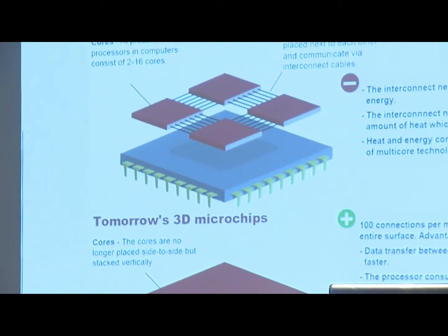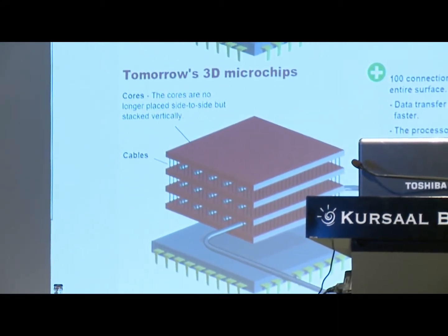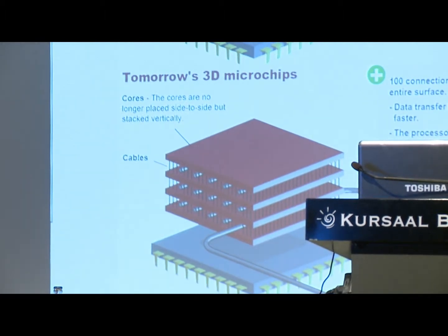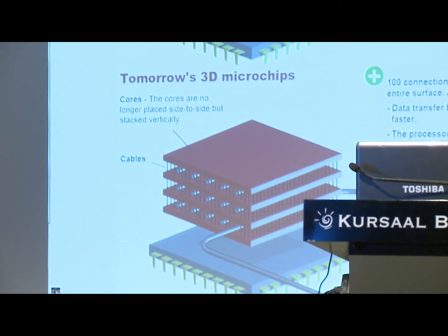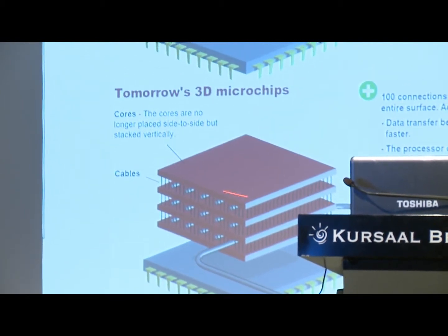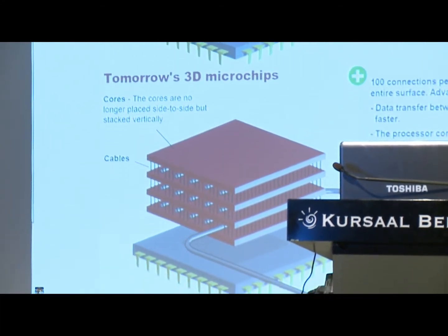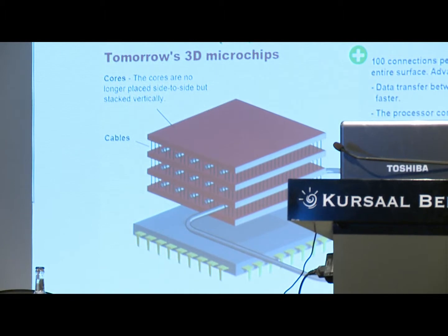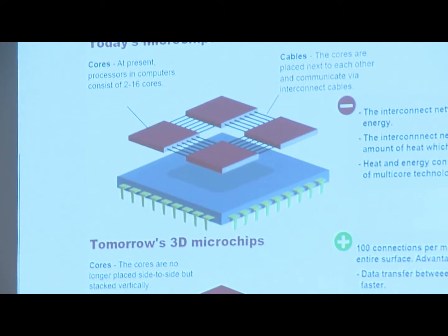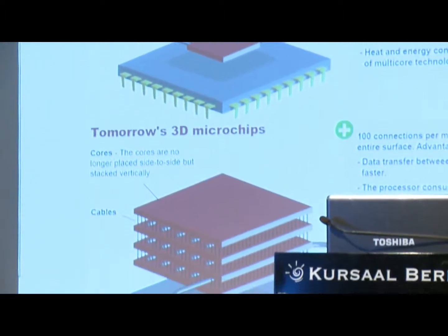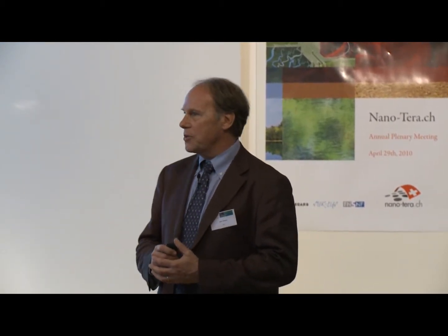The other major challenge is that we may end up with two to four kilowatts of heat to remove from one cubic centimeter — a very high heat flux. A diagram shows a pump to circulate fluid. We'll bring either liquid water inside the 3D chip to take the heat away, or use a refrigerant that partially evaporates inside, removing heat by latent heat to achieve high thermal performance.